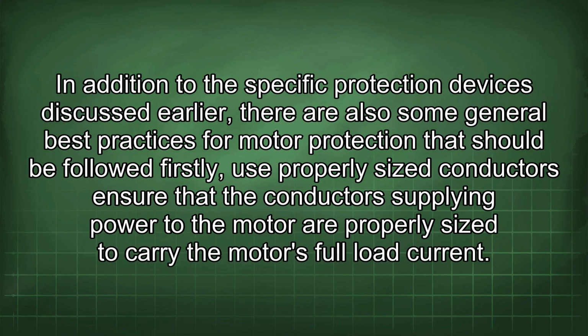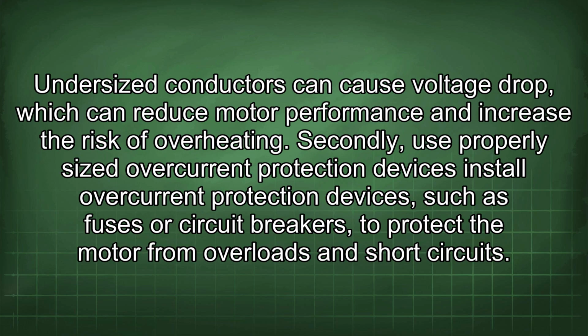In addition to the specific protection devices discussed earlier, there are also some general best practices for motor protection that should be followed. Firstly, use properly sized conductors. Ensure that the conductors supplying power to the motor are properly sized to carry the motor's full load current. Undersized conductors can cause voltage drop, which can reduce motor performance and increase the risk of overheating.